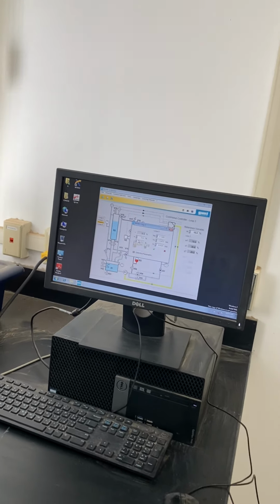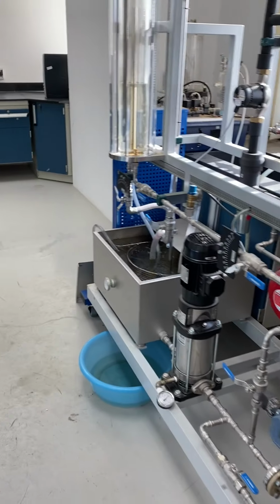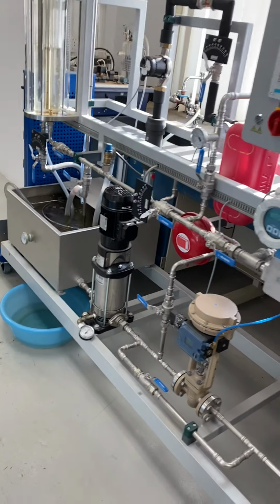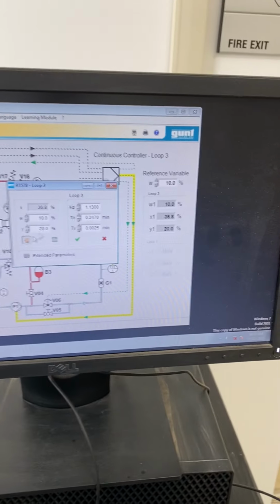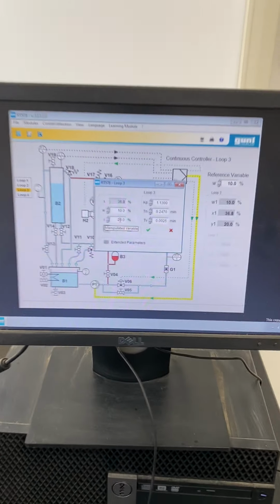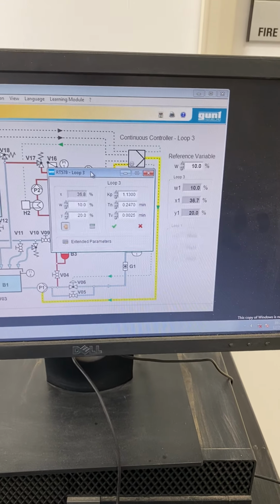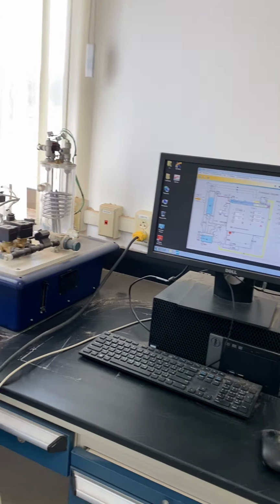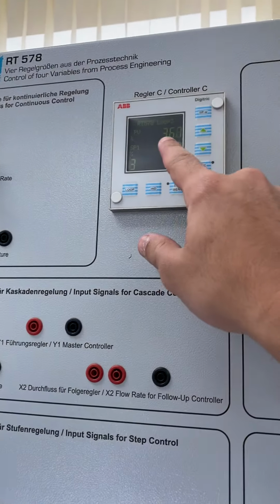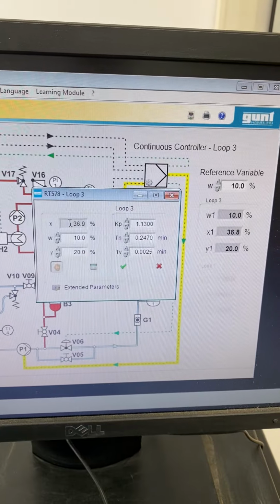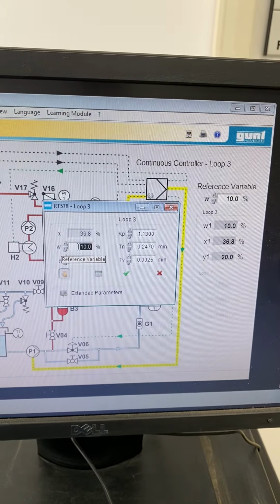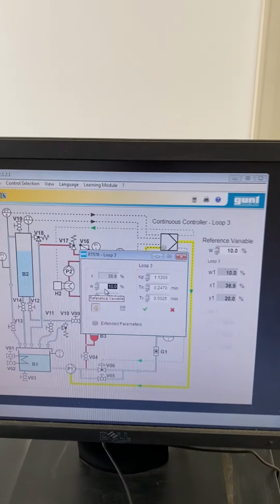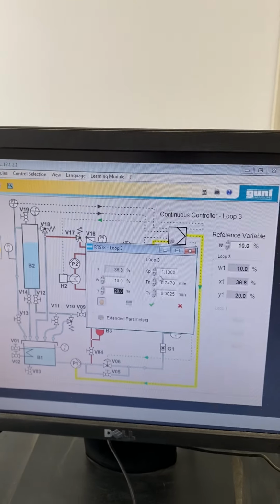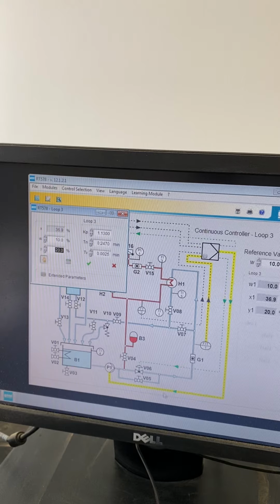Now for the controller, gentlemen, usually we have two scenarios. First of all, if you are going to start up, shut down, or you might have a problem with your automatic control system, you would have to control the process manually. Right? Now when you talk about manual control, I'm trying to say here that in automatic control, the brain of the system, or the computer of the system, is going to compare the current measured value, as you can see, guys, right here, with the reference set point. Okay, this is the set point that we have, guys, and based on the comparison, gentlemen, we will adjust the signal that will go from the controller to the final control element.